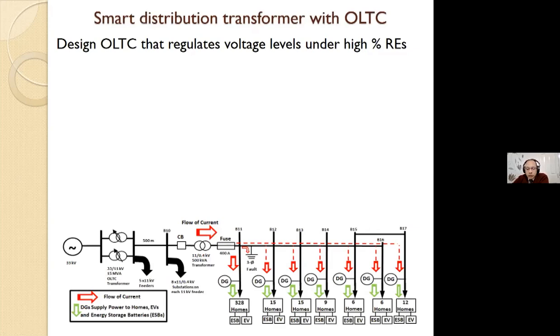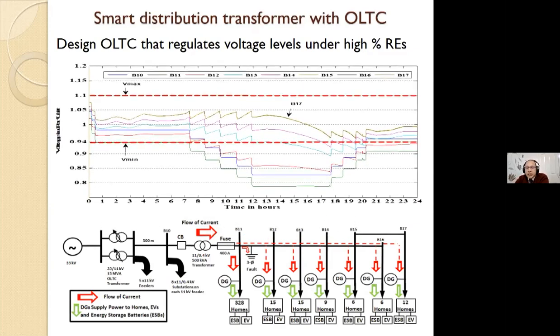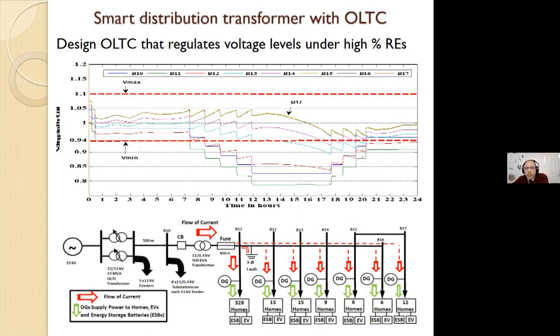Another project we worked on is designing a smart transformer for the distribution network. We all know the voltage needs to stay within certain limits. Keeping within these limits depends on how much energy is generated in the distribution network relative to the load. If you increase the load, the voltage will drop. If you add resources like a distributed generator, the voltage will rise. So having these changes in voltage is not a good thing in the network.